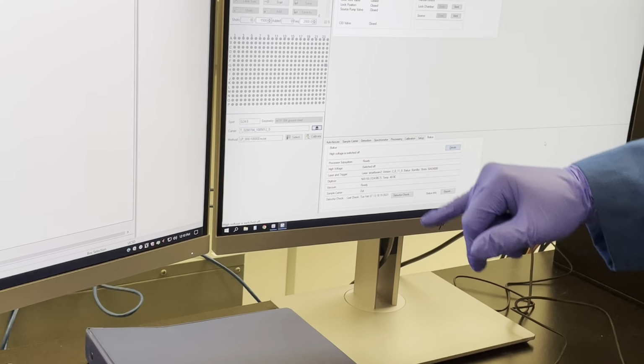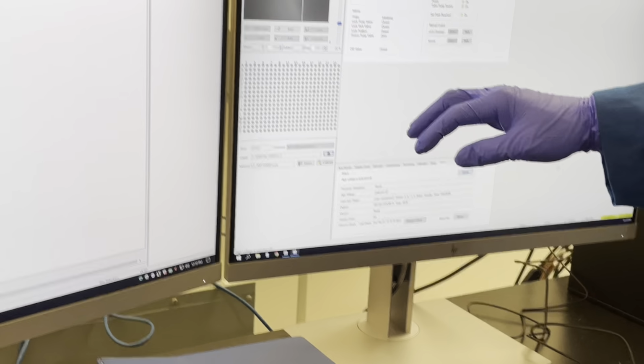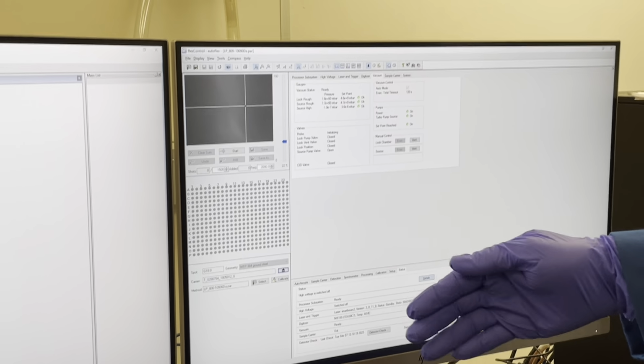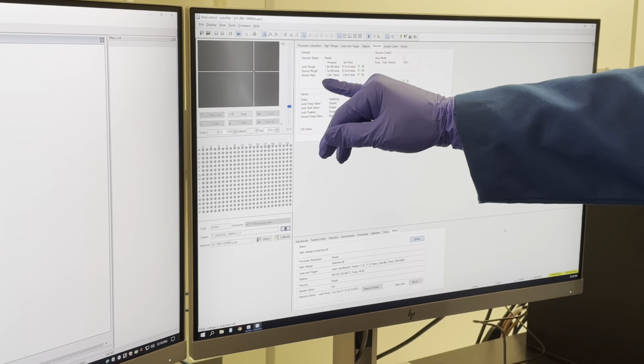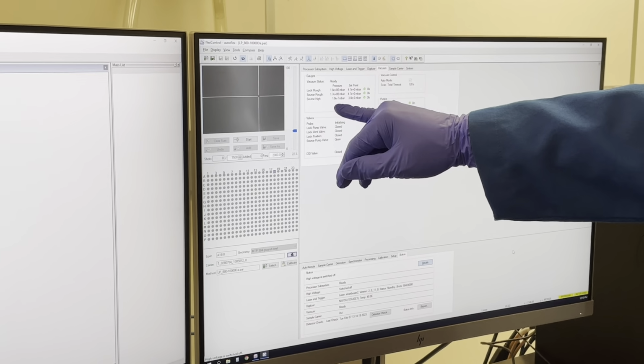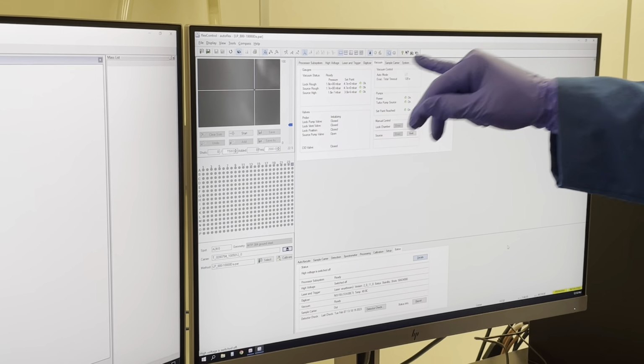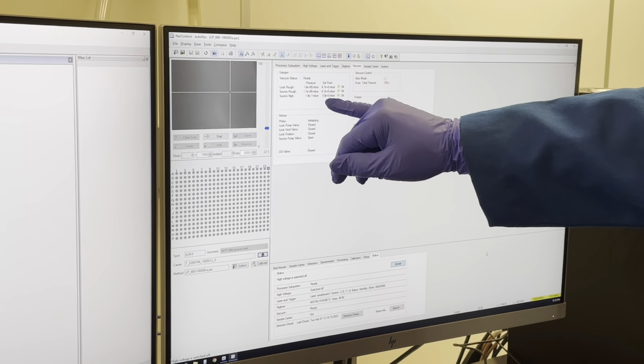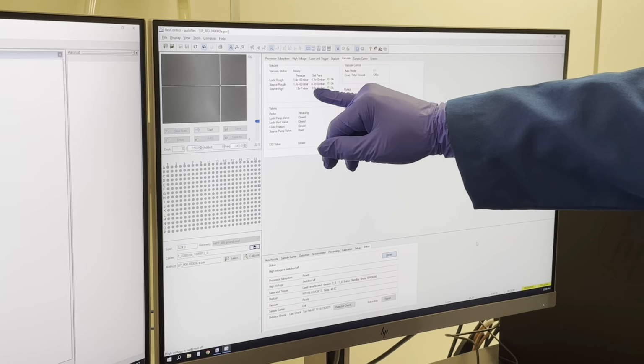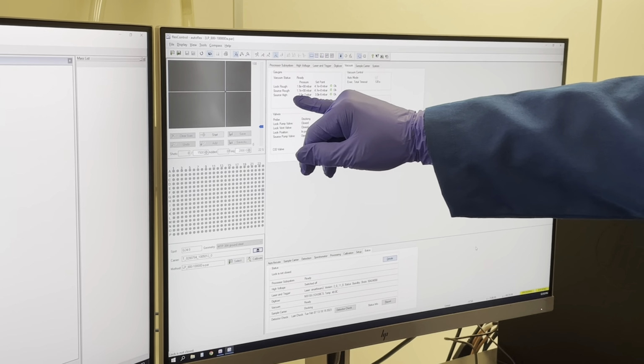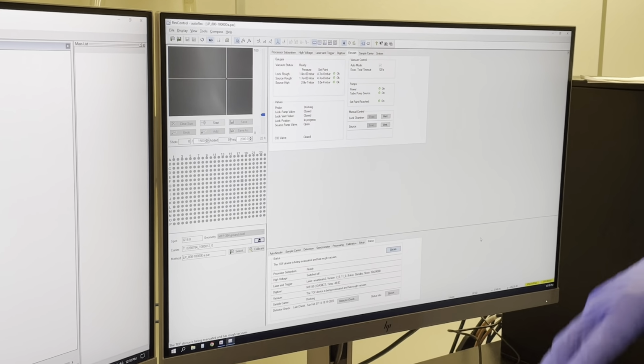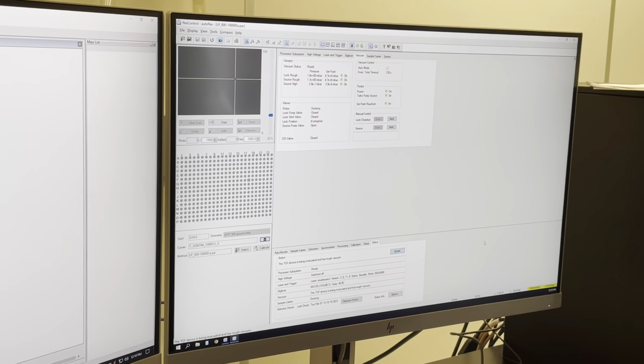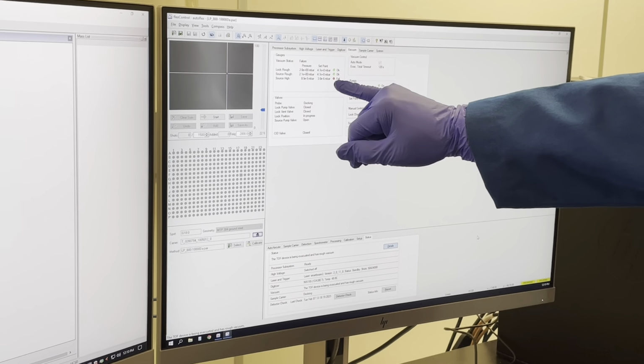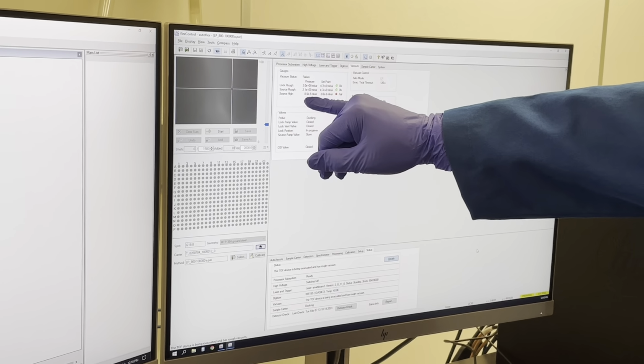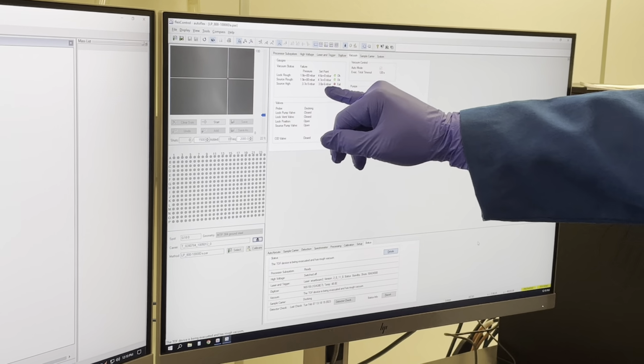That's why the source high reading is going to drop to 10 to minus 4 or minus 5. And then once the gate closes, it's going to power down. So I like this reading to be in the 10 to minus 7 range before we go to the next step. The set point is 3 times 10 to minus 6, but I like the vacuum to be even lower, in the 10 to minus 7 range. So you can see right now it's failing, because this reading is higher than the set point.